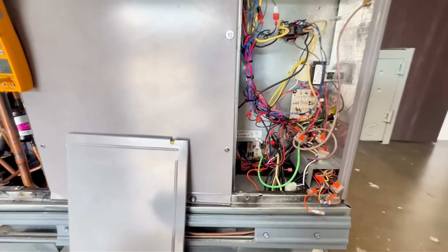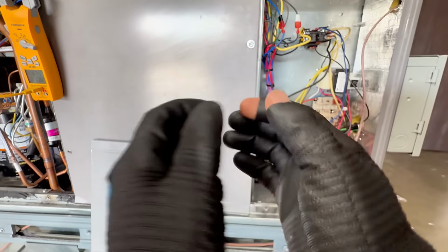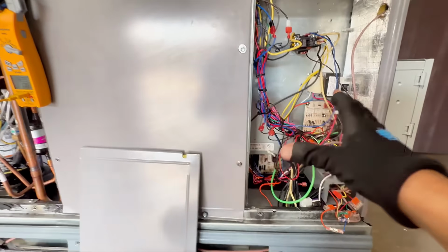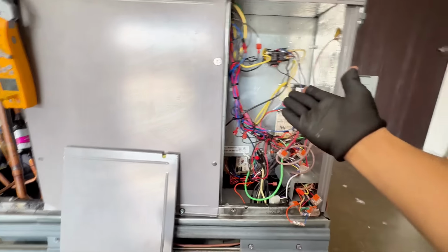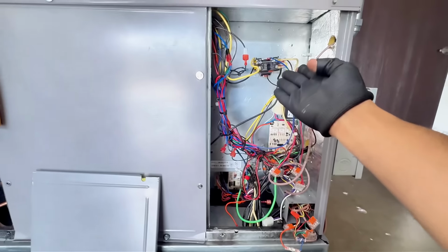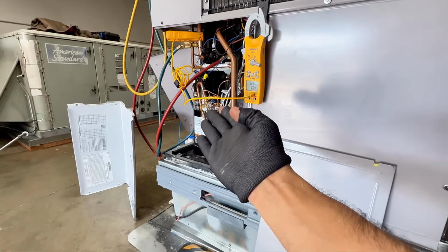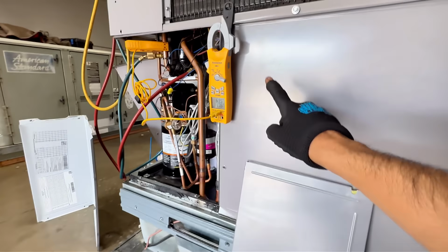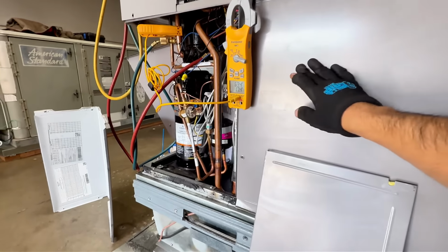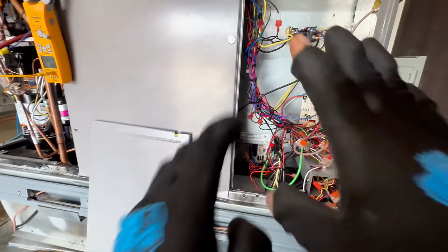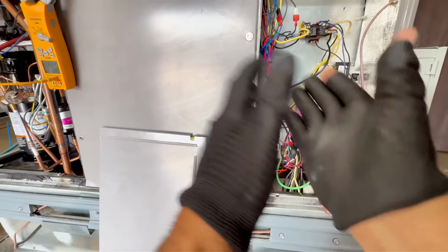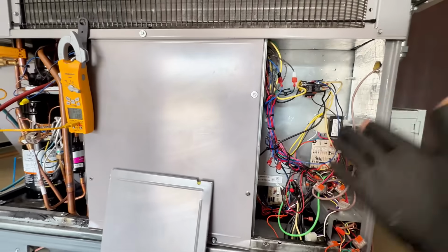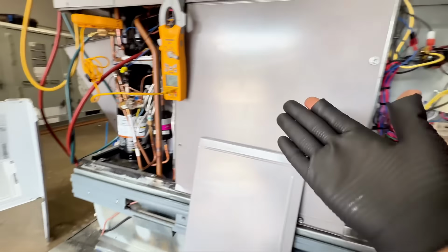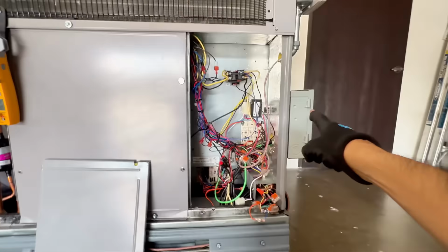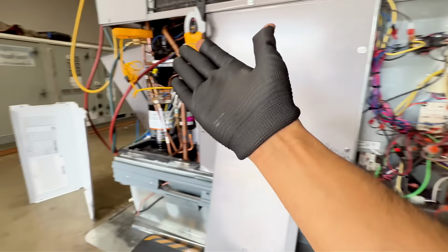But I am going to say one thing: separate your issues. If it's not a low voltage issue, right? If 24 volts turns on, but your compressor doesn't turn on, then it could be a bad capacitor that's in here. There's a bad cap. If you hear it just trying to turn on, check a cap. So try to differentiate if it's a low voltage or a high voltage issue. And typically, if it's a high voltage issue, if it's shorted to ground or for whatever reason, then you would ohm it out, right?